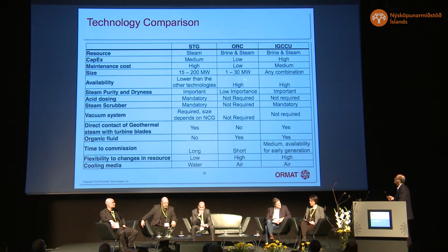Availability, we believe that in an ORC cycle, because there is no connection between the resource and the turbine, the availability is much higher than in the case of direct use of the steam in the steam turbine. Steam purity is important in STG and, of course, in the IGCCU cases, while it is not important in the ORC because the steam is going through the tubes of the heat exchangers. Acid dosing, because we do not reinject all the resource back to the earth, generally is mandatory in STG, which is not required in the other technology. Steam scrubber is mandatory for both technologies that use steam turbines.